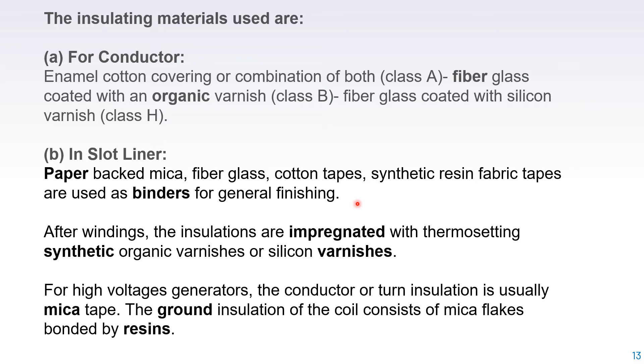The purpose of every insulation layer is to separate conducting paths — otherwise there will be fault or short circuit. Insulation ensures conducting paths do not come in contact with other conducting paths. After winding, the windings are impregnated with thermosetting synthetic organic varnish or silicone varnish. For high voltage generators, the conductor or turn insulation is usually mica tape. The ground insulation of the coil consists of mica flakes bonded by resins.